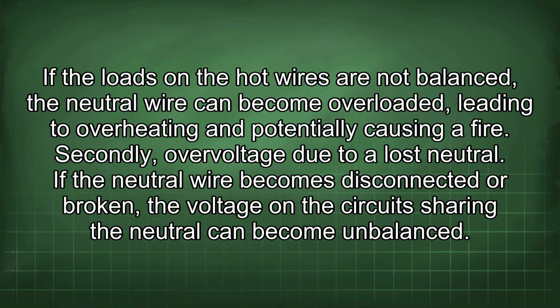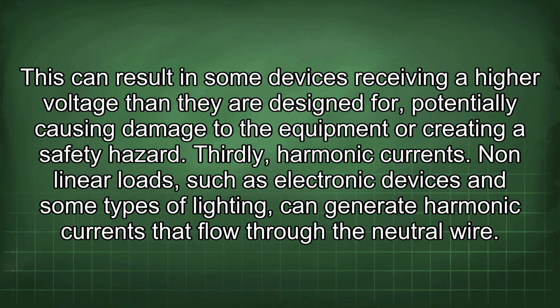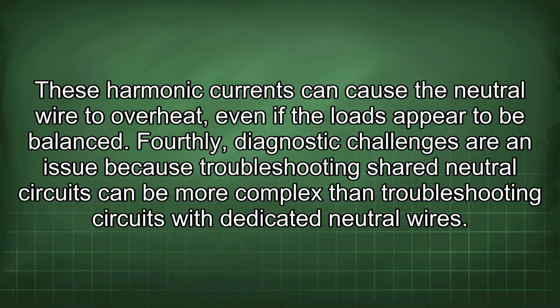Secondly, overvoltage due to a lost neutral. If the neutral wire becomes disconnected or broken, the voltage on the circuit sharing the neutral can become unbalanced. This can result in some devices receiving a higher voltage than they are designed for, potentially causing damage to the equipment or creating a safety hazard. Thirdly, harmonic currents. Nonlinear loads, such as electronic devices and some types of lighting, can generate harmonic currents that flow through the neutral wire. These harmonic currents can cause the neutral wire to overheat, even if the loads appear to be balanced.